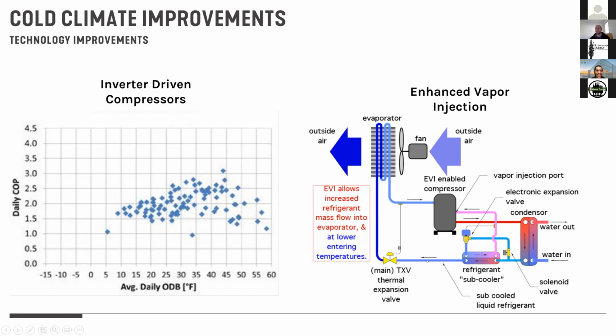That allows us to subcool the refrigerant that's going to the outdoor unit, or is in the outside half of it if it's a monoblock style system. That increases your delta T on the heat exchanger and is going to allow you to pull more heat out of very low or sub-freezing outside air temperatures. The super cold refrigerant goes back to the compressor and then is blended with the warmer refrigerant that was peeled off earlier. So there are strategies to do multi-loop refrigeration cycles or paired refrigeration cycles to get better delta T's across your heat exchanger. And those technologies are critical for cold climate applications.